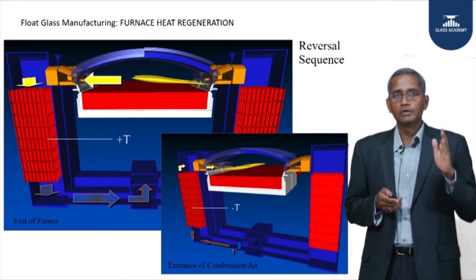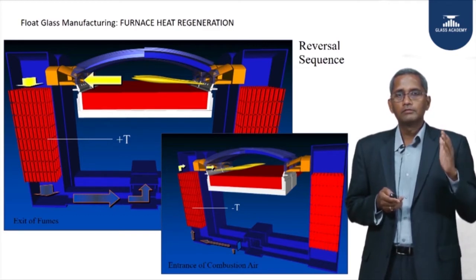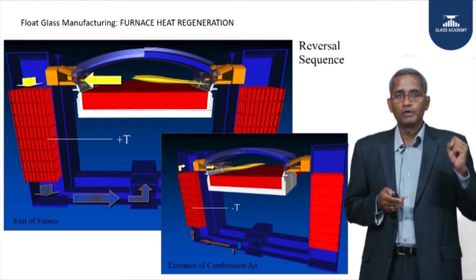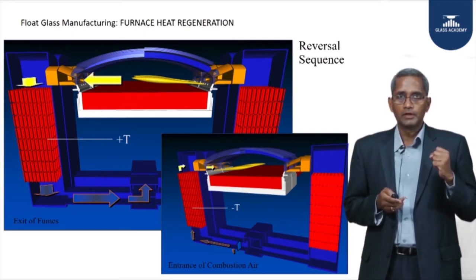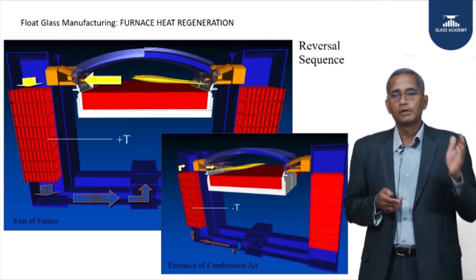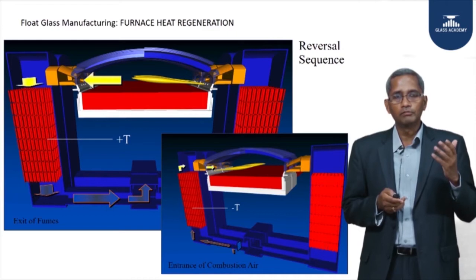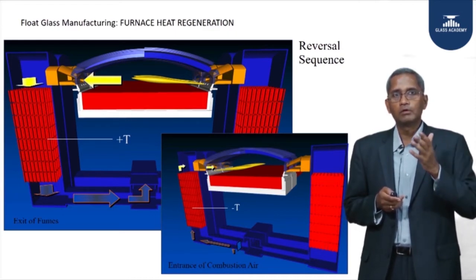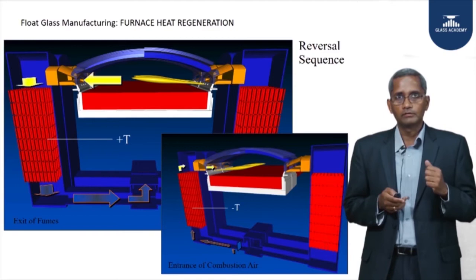The combustion air now passes through the regenerator which is already soaked with heat. This regenerator, which absorbed heat from the flue gas coming at 1450°C, takes the atmospheric-temperature combustion air and heats it so that it enters the furnace at 1300 to 1350°C. So what we lost at 1450°C, we have majority regained back as preheated combustion air for the next 20 minutes.